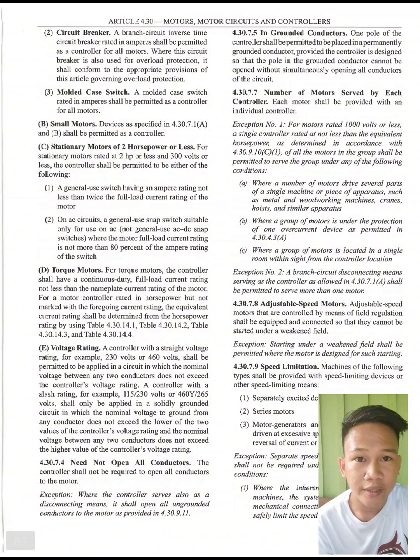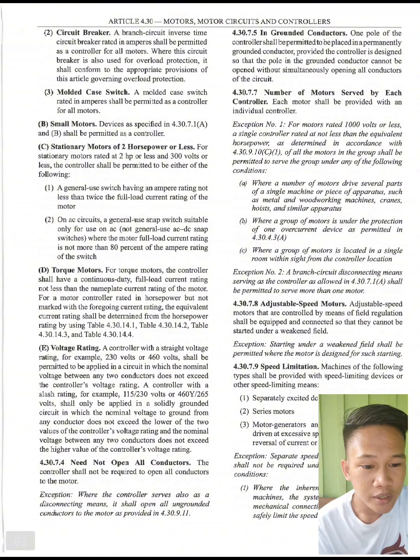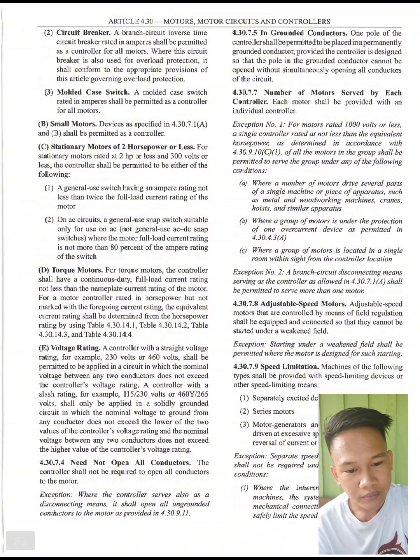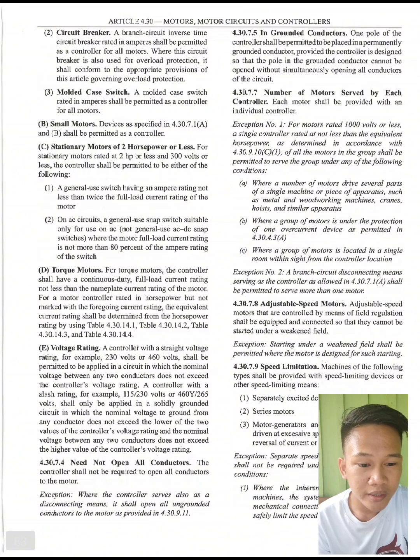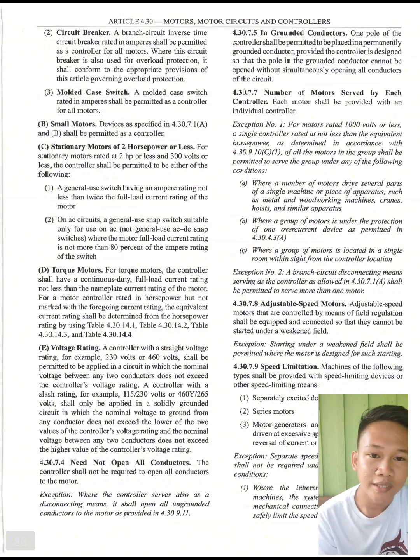Next we have 4.30.7.8. Adjustable speed motors. Adjustable speed motors that are controlled by means of field regulation shall be equipped and connected so that they cannot be started under a weakened field. Exception: starting under a weakened field shall be permitted where the motor is designed for such starting.